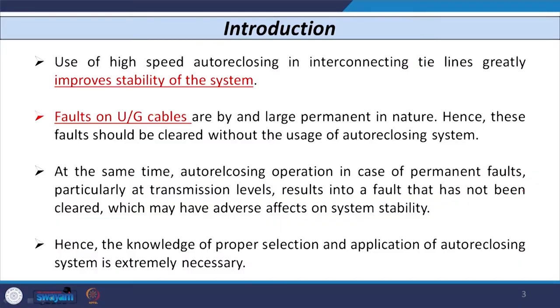The use of high-speed auto reclosing in tie lines — when a big tie line is connected between two areas — can definitely improve the stability of the system. One important point is that faults on underground cables are usually permanent in nature, so such faults do not need auto reclosing. We should use the auto reclosing system only for overhead conductors, not for underground cables.